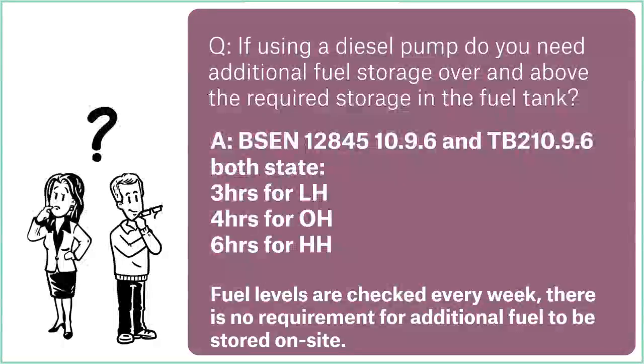top it up again. So I think I'm right in saying that for most diesel pumps the actual fuel tanks are bigger than this. They're kind of 8 hours worth of fuel, and I guess that's just convenience. You don't have to keep topping it up every week. You've got yourself again a buffer over the required standards. I hope I'm making this clear. So yeah, that's what the standards say you need on site at any time, which is already a surplus of fuel over the duration of the sprinkler system. But it obviously is good to have even more than that, so that you're not having to top it up very regularly.